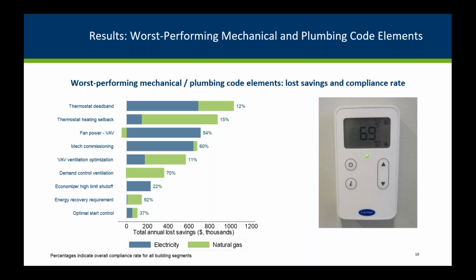What I'd like to emphasize here is that overall, like Jeanette mentioned, the lost savings predominantly result from control elements rather than equipment efficiency. The market for HVAC equipment has shifted enough that commonly available product lines already meet code efficiency ratings. For controls, on the other hand, many settings and sequences are still programmed manually during installation, making them prone to error, especially when the sequence of operations is not well documented.